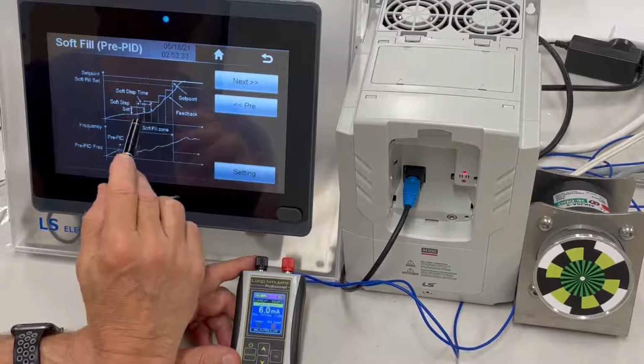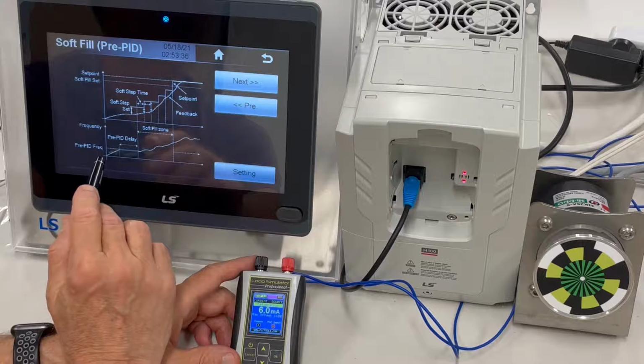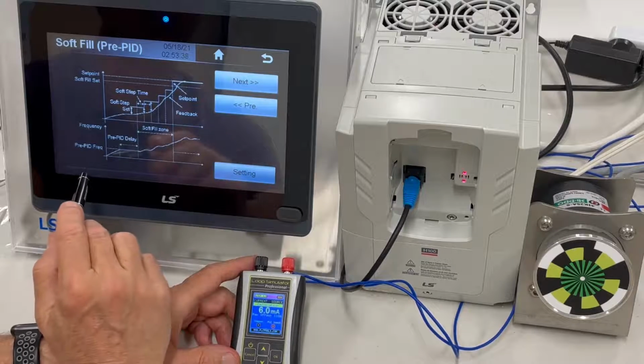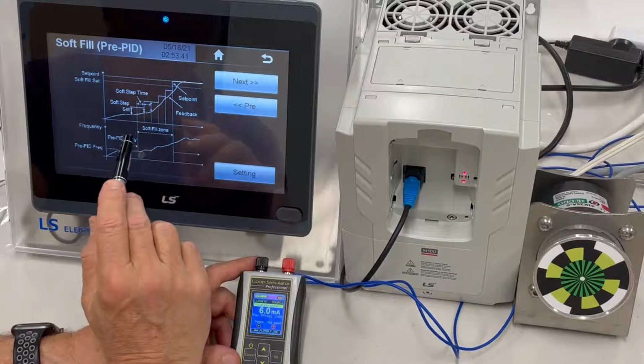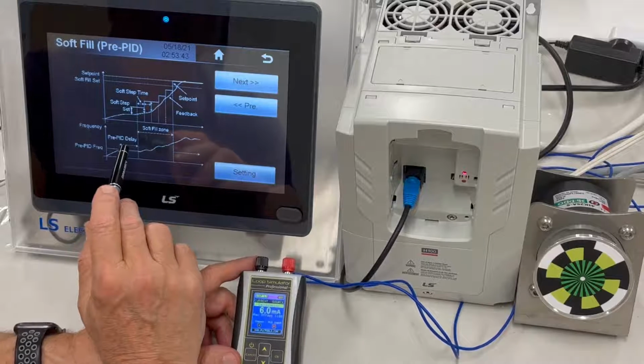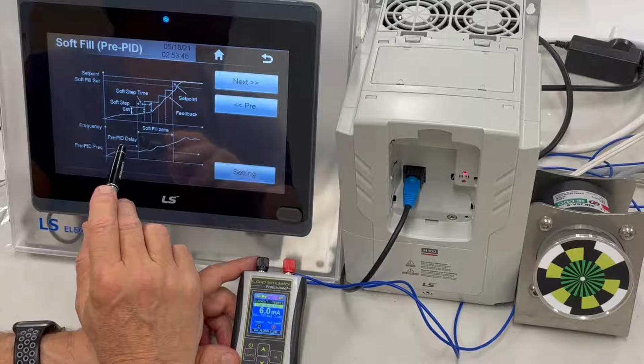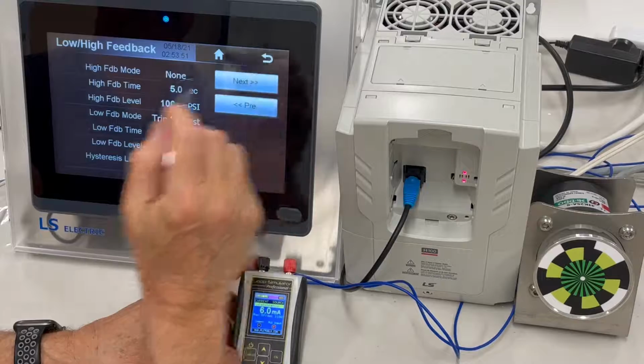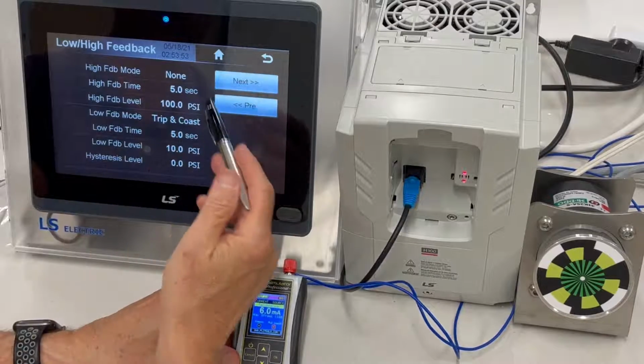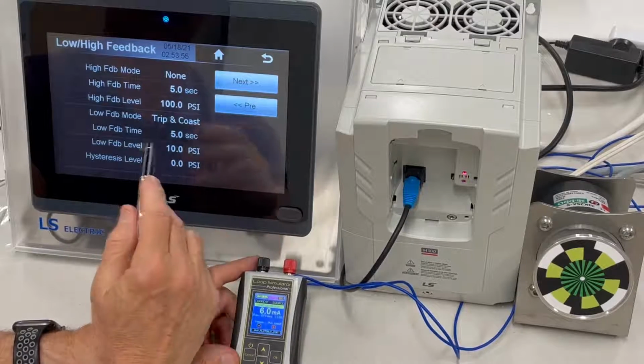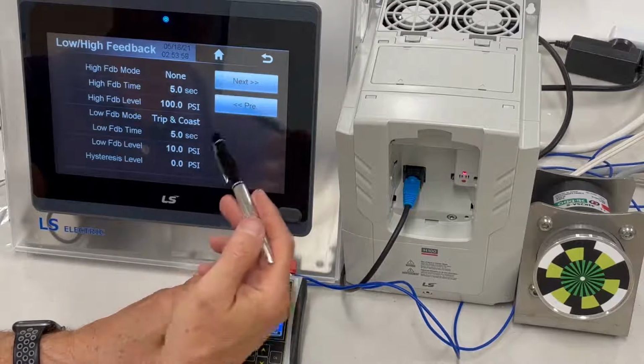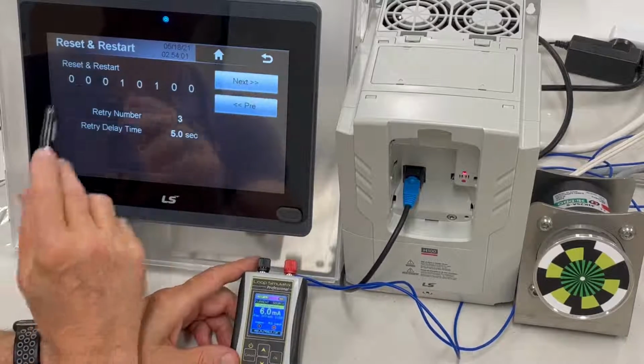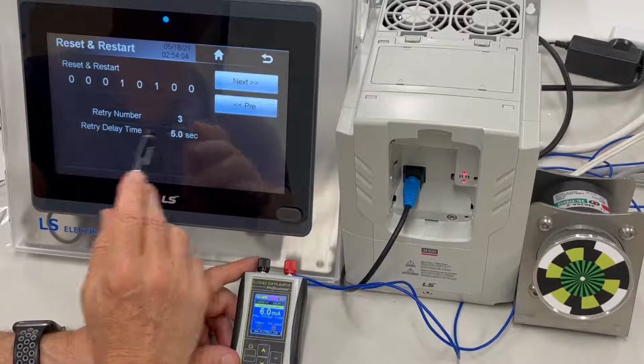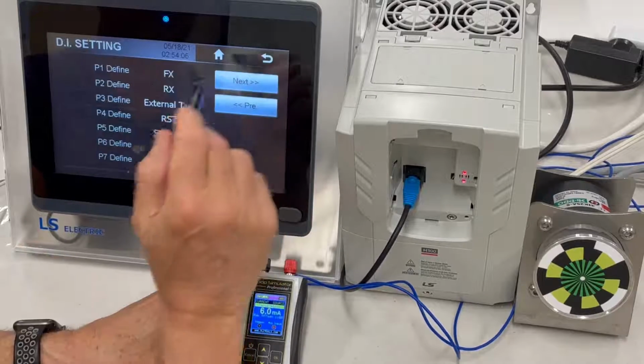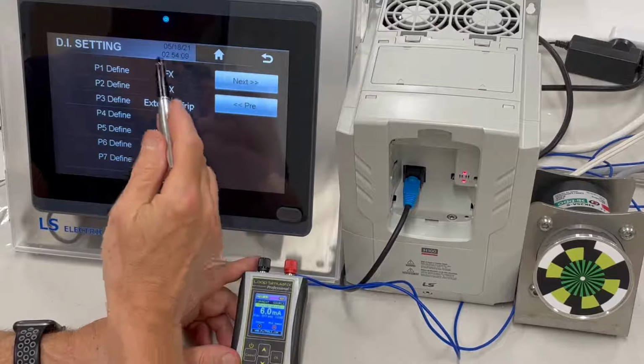Here's the soft fill zone, and that just stair steps you when you're starting at 0 to get to a set point that's high. You don't want to run very fast up there, because the drive could accelerate fast, and that might cause issues with your pump, and we don't want to damage it, so we want to gradually get up to the set point in a controlled manner. So a low high feedback, here's your settings on that, different types of feedback modes and timings and PSI levels and hysteresis. Reset and restart, so we have it for 3 retries, 5 seconds apart. And then here's your direct input settings.